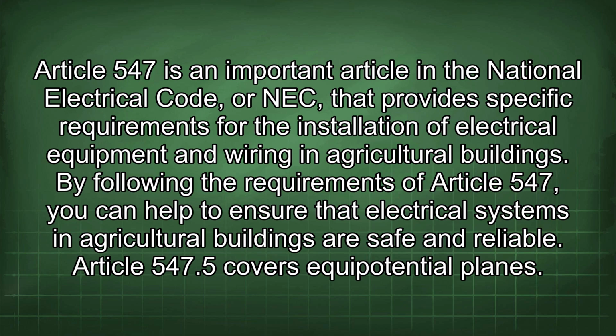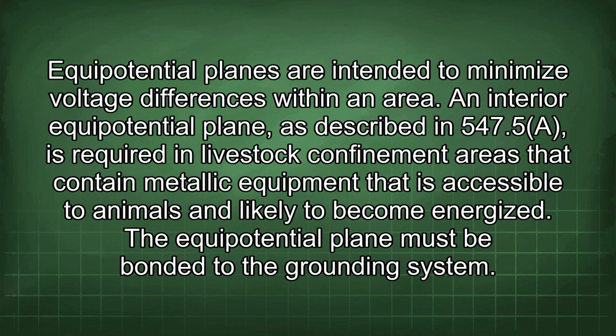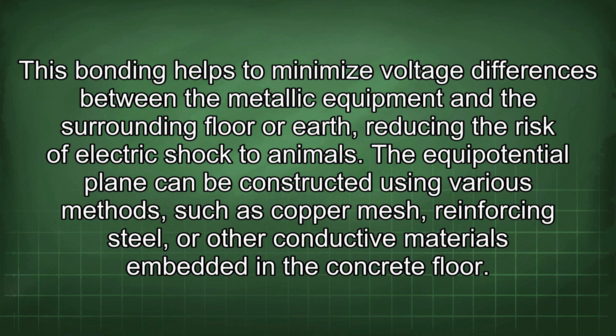Article 547.5 covers equipotential planes. Equipotential planes are intended to minimize voltage differences within an area. An interior equipotential plane, as described in 547.5(A), is required in livestock confinement areas that contain metallic equipment that is accessible to animals and likely to become energized. The equipotential plane must be bonded to the grounding system. This bonding helps to minimize voltage differences between the metallic equipment and the surrounding floor or earth, reducing the risk of electric shock to animals.